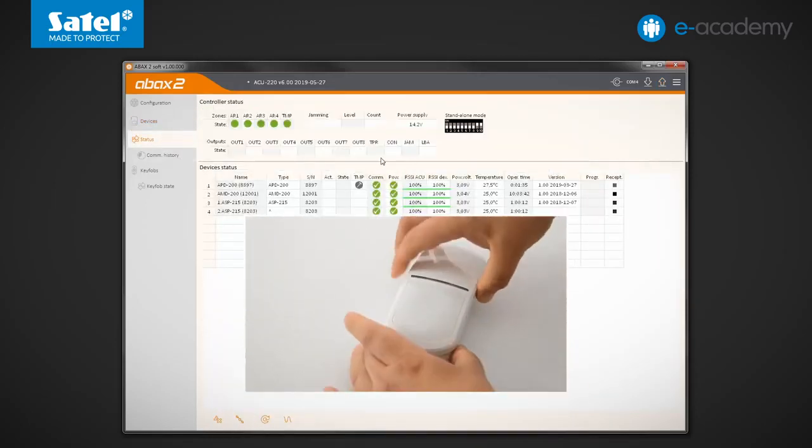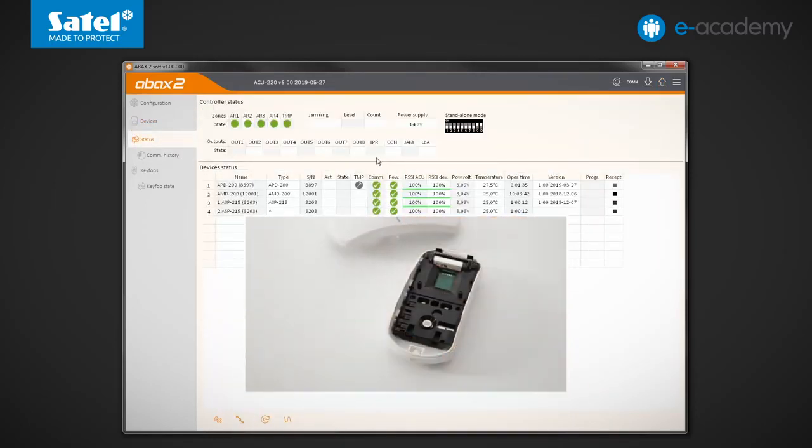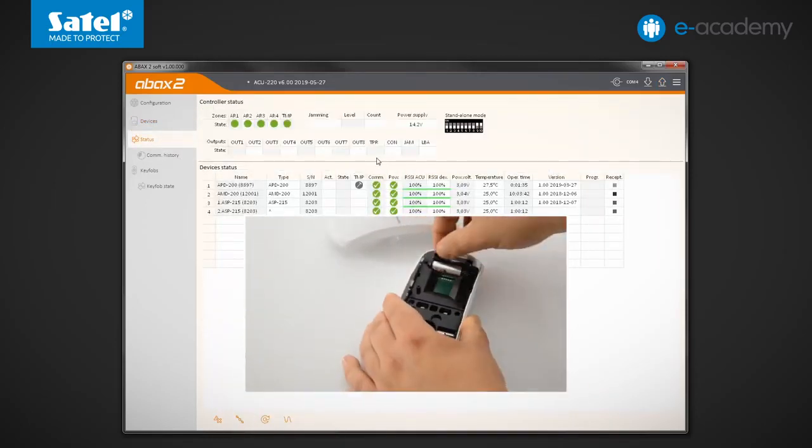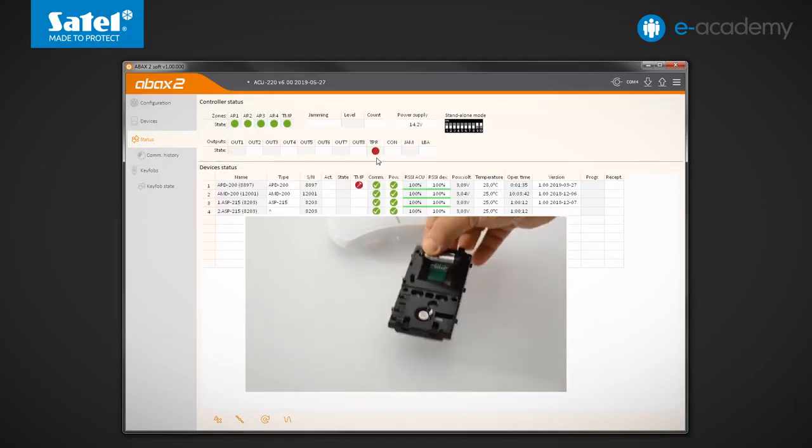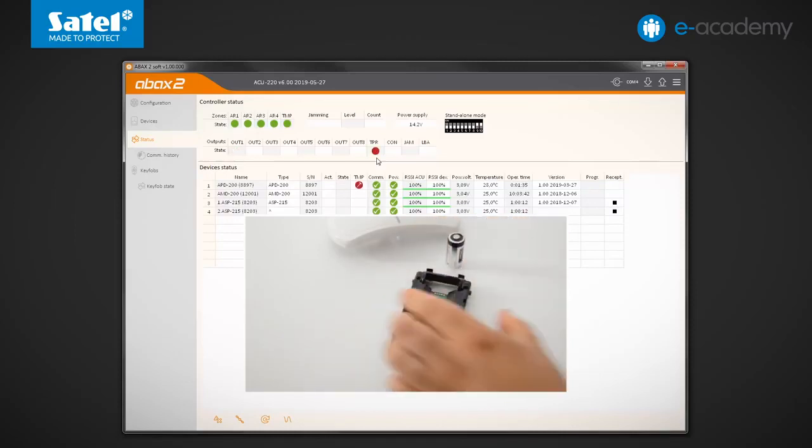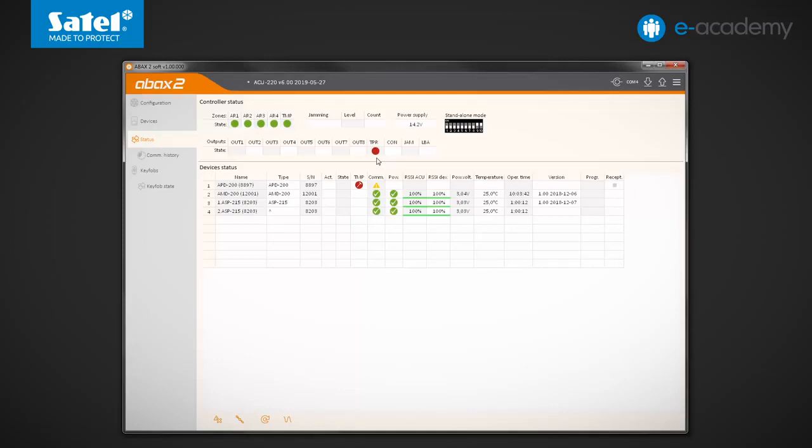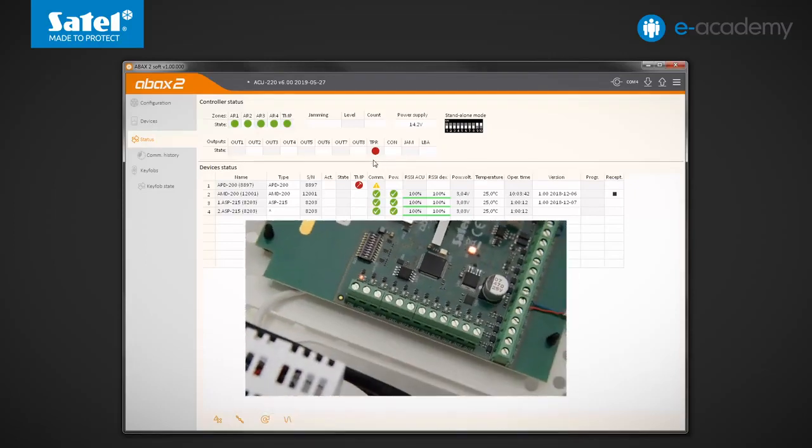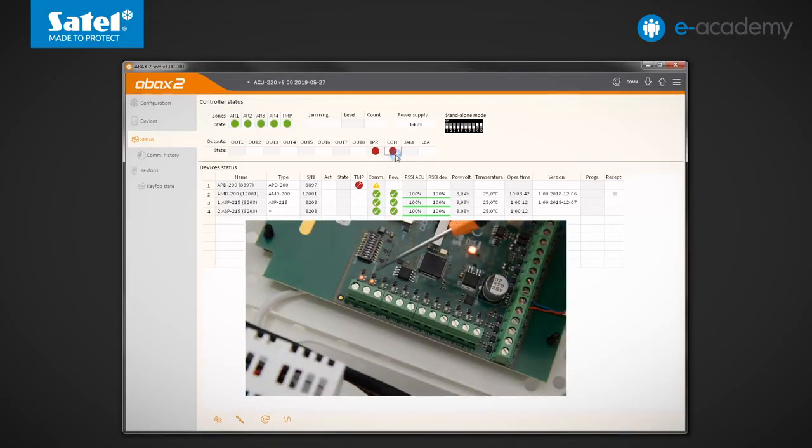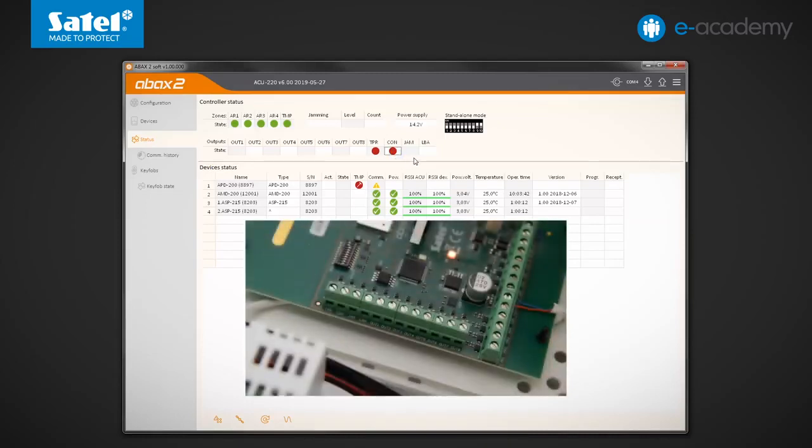Open the detector enclosure again and remove the battery. Initially, only information about tamper is available. We have to wait more than 12 seconds, which is longer than one communication period. OK, a suitable icon appears next to the detector indicating a communication problem. At the same time, the CON output state changed to active.